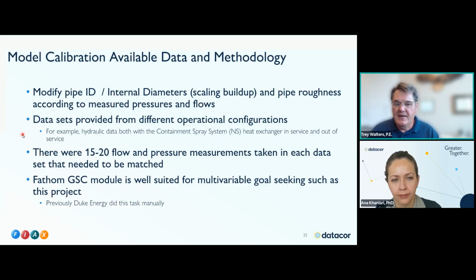Duke Energy had 3 different data sets of different operational configurations. So it wasn't just measurements from one operation. They had 3 different operations of this particular piping system. So we were trying to work with them to calibrate so that they would get scaling and roughness that would match not just one data set, but match 3. So that was quite the challenge.